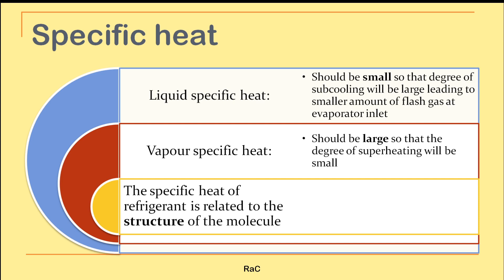The second important property is specific heat. There are two kinds: liquid specific heat and vapor specific heat, because the refrigerant undergoes phase change in both the evaporator and the condenser. Liquid specific heat should be small so that sub-cooling is large, leading to a smaller amount of flash gas at the evaporator. Vapor specific heat should be large so that the degree of superheating will be small.